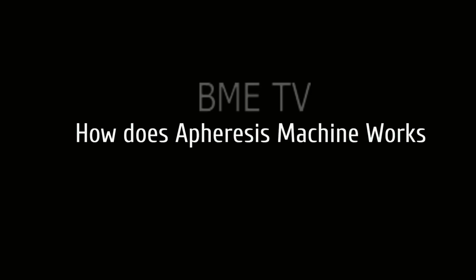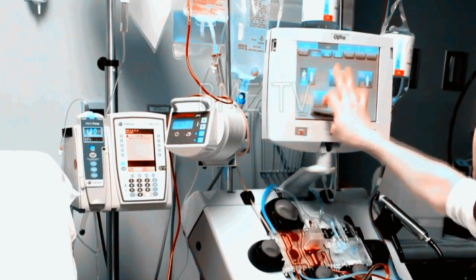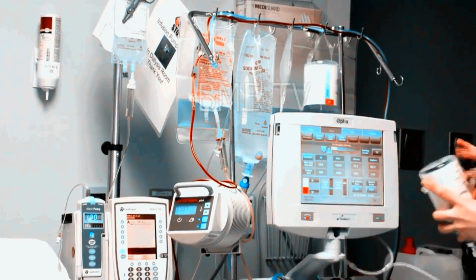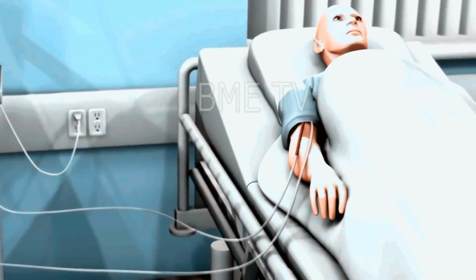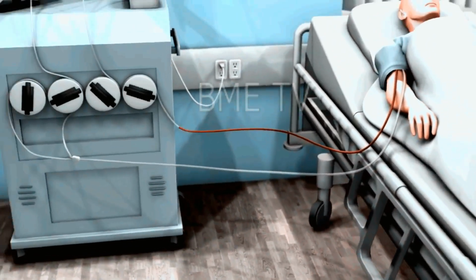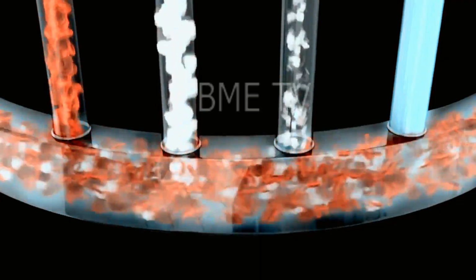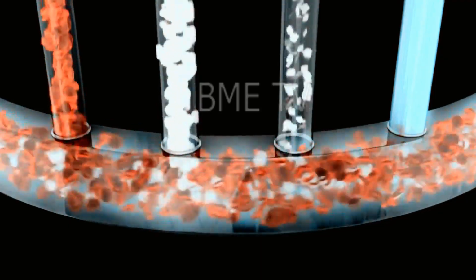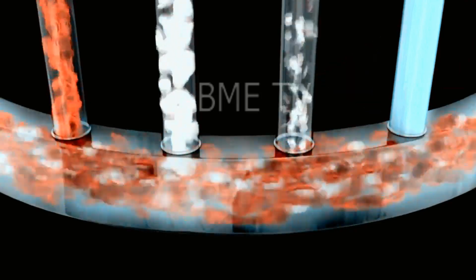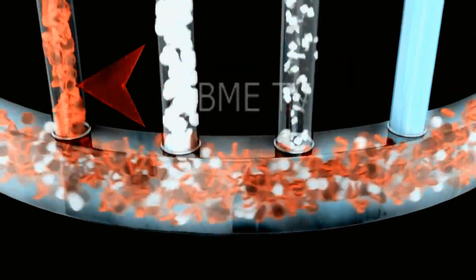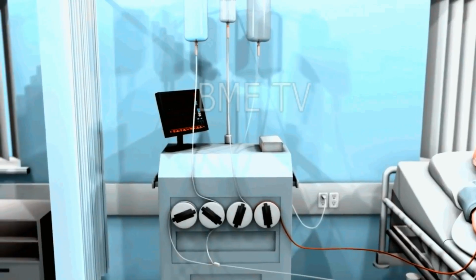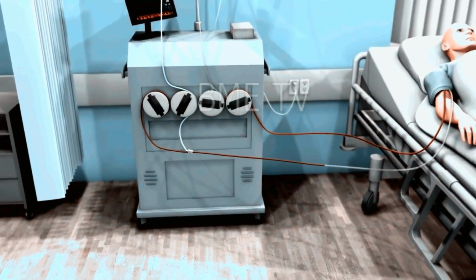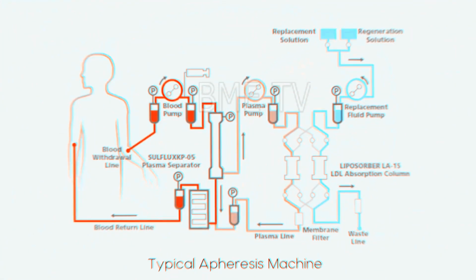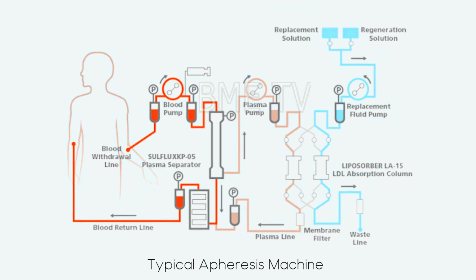How does the apheresis machine work? Apheresis units incorporate polyvinyl tubing that draws blood from the patient and moves it through centrifuges and/or filters to separate blood products. The blood is then returned to the patient via tubing or is collected in bags, often suspended from a pole, for donation or disposal. A display and control panel allow the operator to program the unit and view progress and/or alerts. Safety features include pressure sensors, ultrasonic air bubble detectors, optical fluid level detectors, and dry heat fluid warmers. The warmers prevent hypothermia caused by infusing low-temperature fluids. The unit may have wheels or it may be placed on a cart.